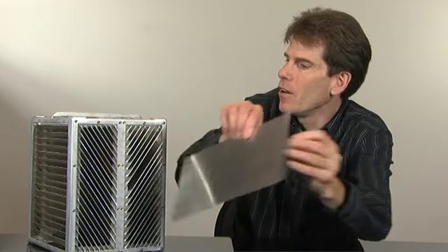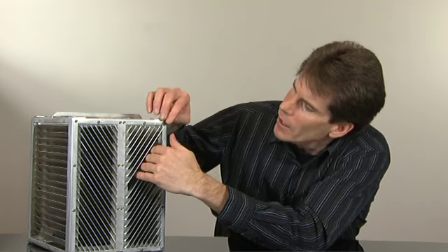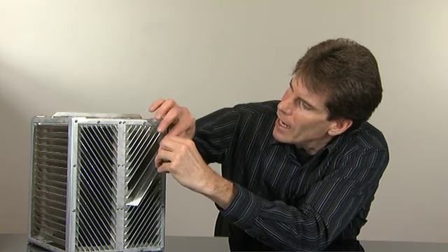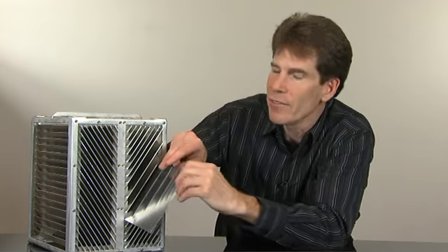Typically we ship a plate pack with every other plate in place. By doing that, we give the versatility of upgrading if there's the need, or you can pull plates out if they're so high in solids that the problem is in maintenance. So, for instance, we can pull out, say, every other plate on our coalescer plate pack system in the field. So you can see here that if we do that, we're able to change the plate gap in the field.